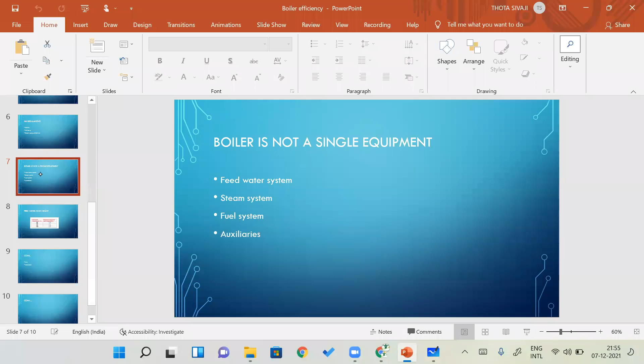It is around three things. If you have a closed vessel where you are trying to convert liquid into vapor, by heating and increasing the temperature of water, with volume greater than 22.75 liters, it should comply with IBR regulations. And then pressure more than 3.5 bar gauge; at that time also it should pass the IBR regulations. The thickness, the operating pressure, and the design pressure of a boiler should meet the IBR regulation.